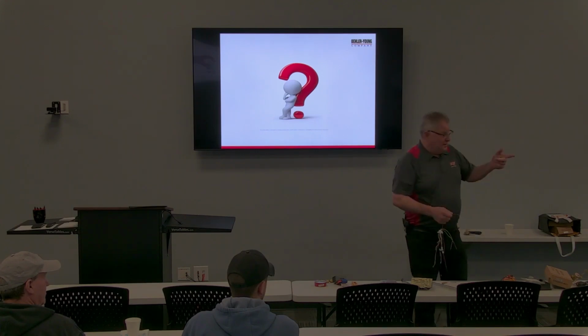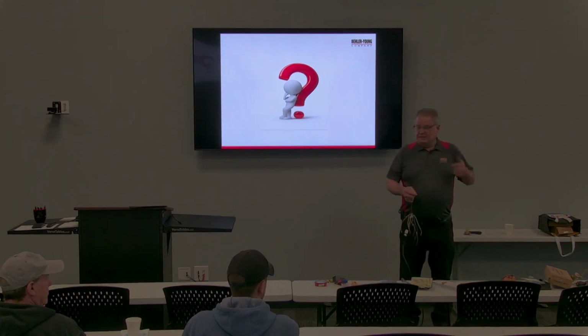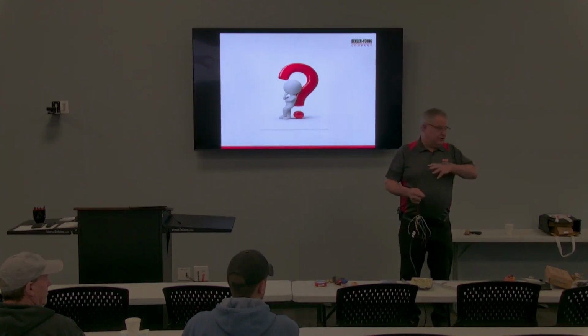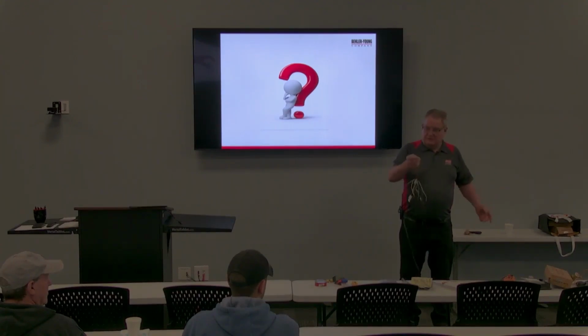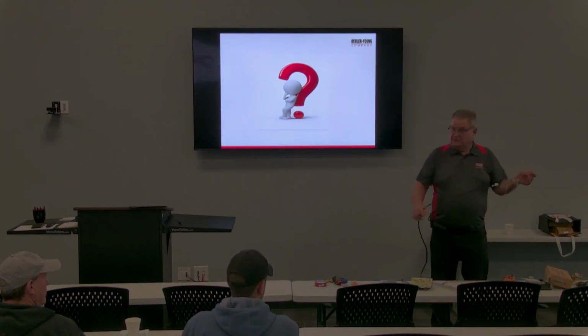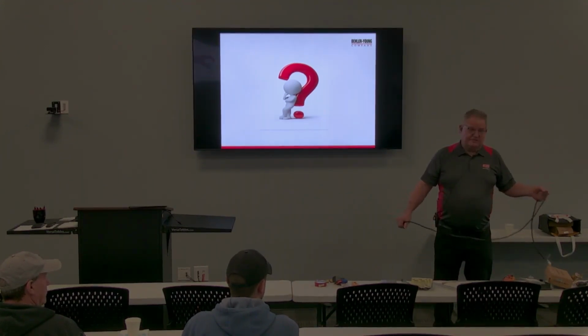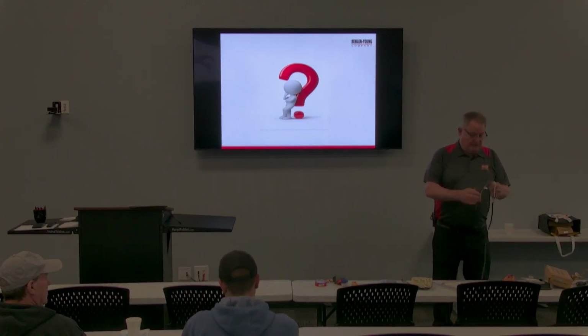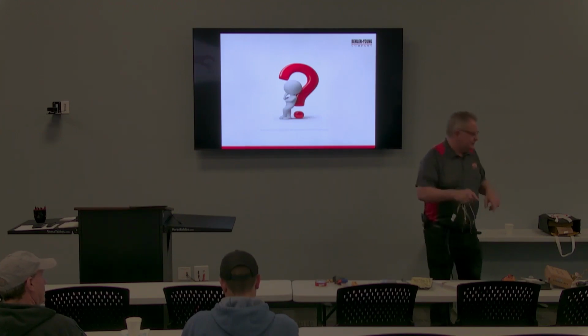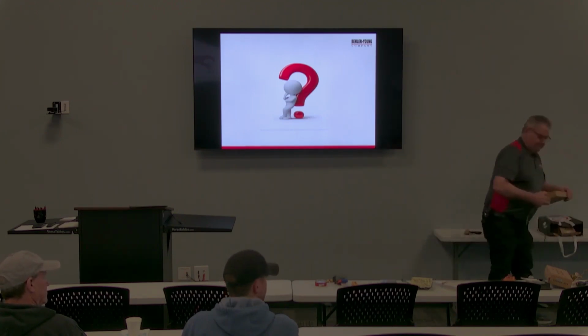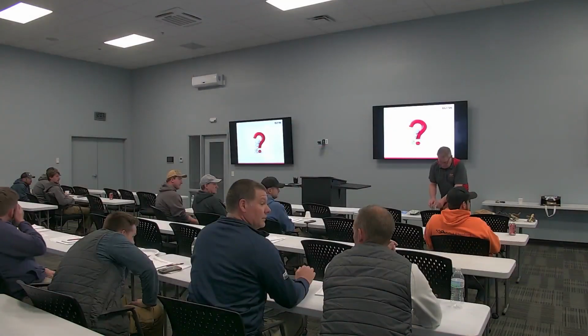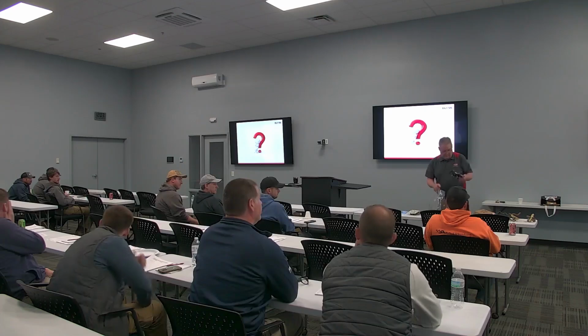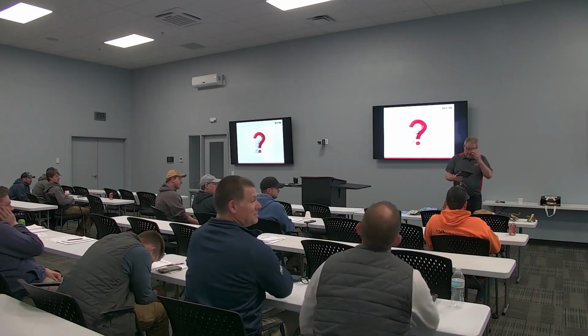And there's another reason, as you made me think of, because if a limit trips, it shuts off all the 24 volts. If the fuse blows, it kills the entire board. This would still be powered, because the fuse is after this. So that's why they're powering this from there, because you don't want the mitigation board to be disabled just because you got a limit trip. So everybody clear on that? Yeah, that's a good point, because when you're looking at the two secondary terminals, I think it says sec 1, sec 2. Yeah, that's the 24 volts, and it's further down the stream. So don't be tempted to just cut the terminal off and wire it into R.